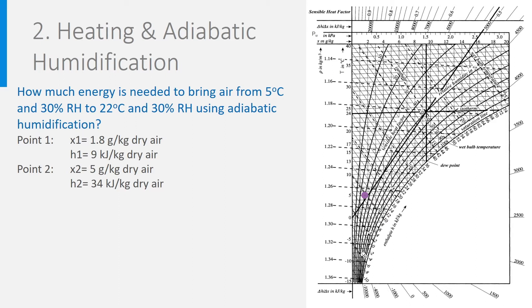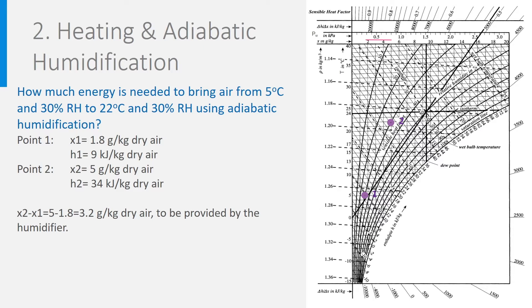What if we now also want to control the humidity and make sure the relative humidity is 30 percent after heating? We start again from point 1 at 5 degrees, 30 percent relative humidity, and absolute humidity 1.8 gram per kilogram dry air. Point 2 at 22 degrees and 30 percent humidity has absolute humidity 5 gram per kilogram. So to go from 1 to 2 we need to heat and to add water vapour to the air. The quantity of water vapour that must be added is 5 minus 1.8 equals 3.2 gram water vapour per kilogram dry air.